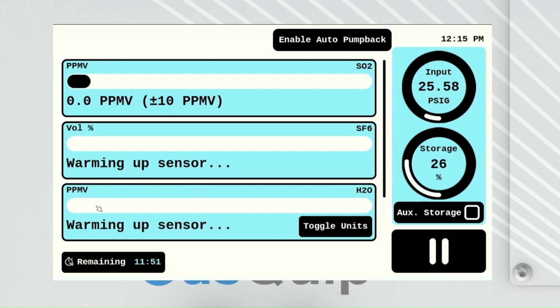The reason for that is that the H2O sensor runs a heater for 5 minutes on the first test of the day, or anything that is within the last 24 hours, it'll reset that timer. So that H2O sensor will heat up for 5 minutes prior to testing. The reason it does that is to help burn off some of the residual moisture that creeps into the device or might be left over from previous tests. So that heater will run, try to burn off some of that so that you get a good result on the first test. Any subsequent test that you run will run for about 7 minutes as opposed to 12 on the first.